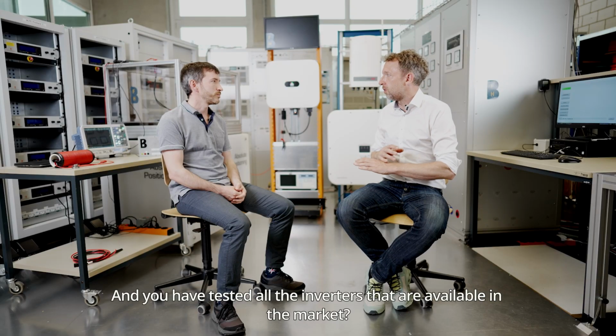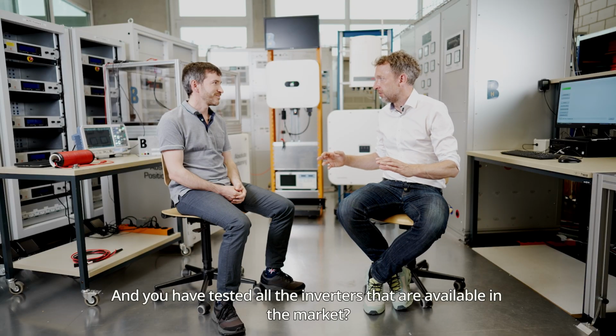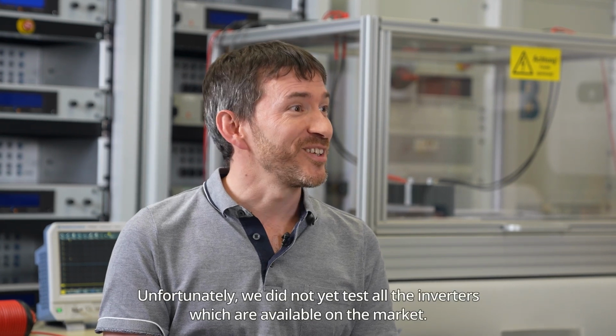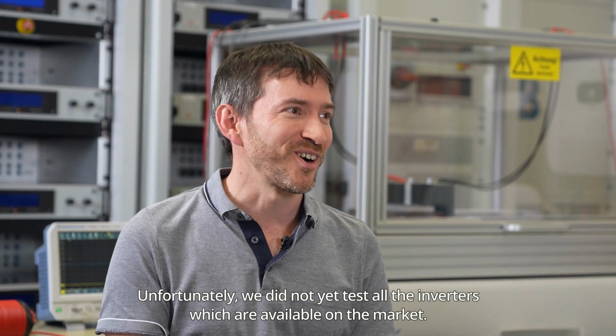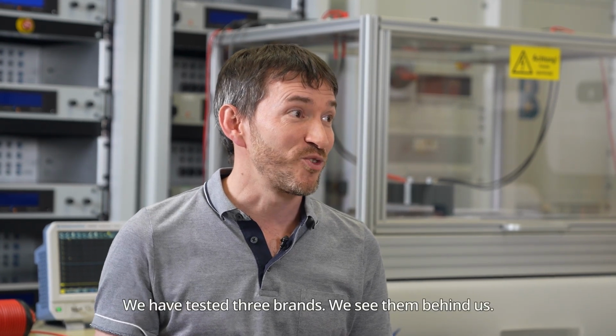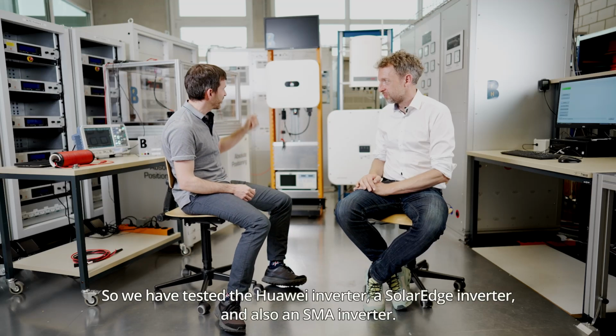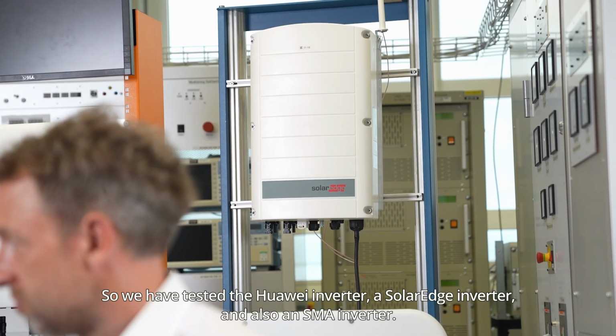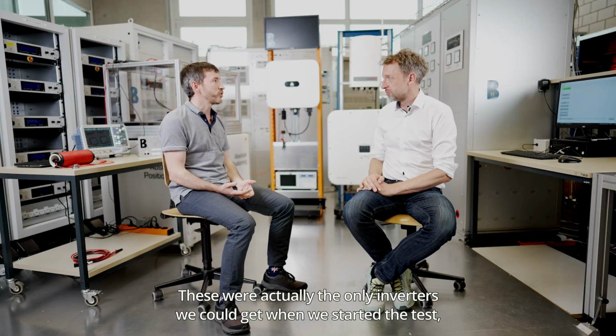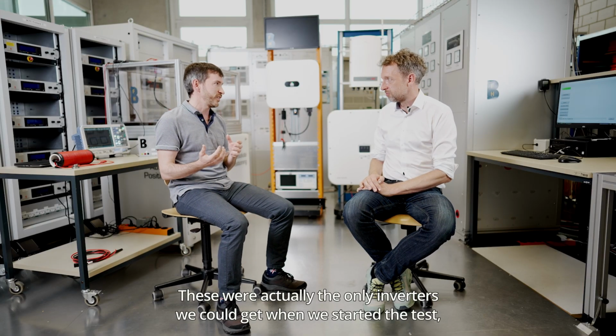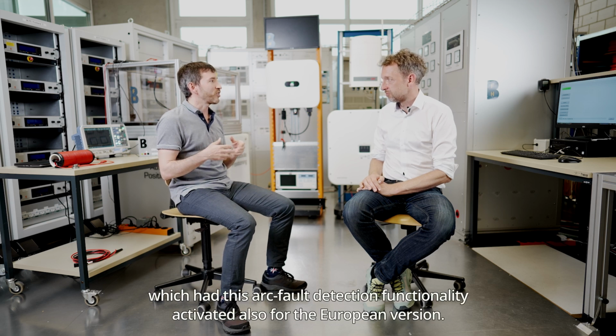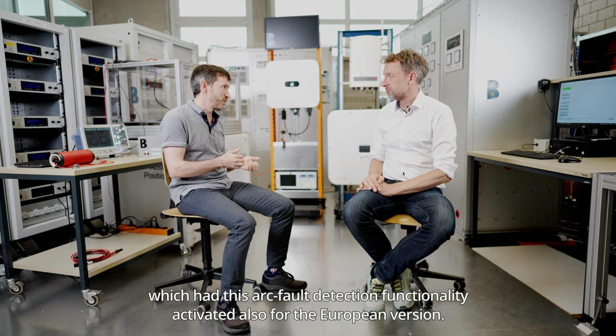And you have tested all the inverters that are available in the market? Unfortunately, we did not yet test all the inverters which are available on the market. We have tested 3 brands. We see them behind us. So we have tested a Huawei inverter, a SolarEdge inverter, and also an SMA inverter. These were actually the only inverters we could get when we started the tests, which had this arc fault detection functionality activated also for the European version.